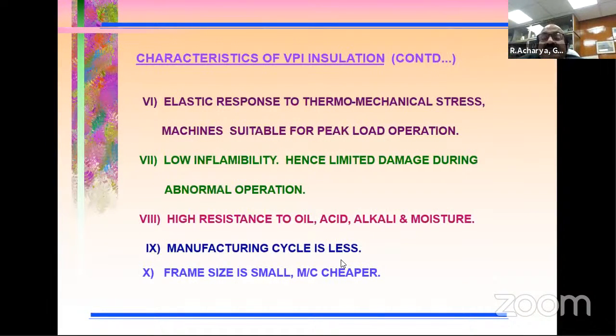You can say the elastic response. This is what I wanted to highlight, one important factor of the VPI insulation system: because of the elastic response, when the machine runs at different loads due to flexible operations, naturally the thermomechanical stresses will be there in the winding and the core. The adherence and the bondage matter. If the bond breaks, then there is a possibility of mechanical damage, thus resulting in electrical failure.